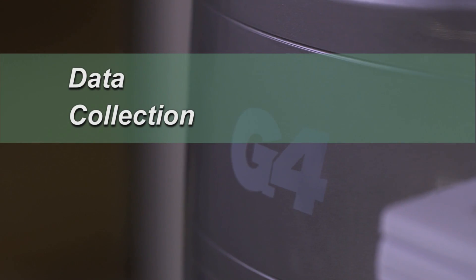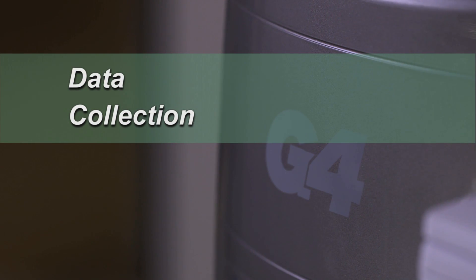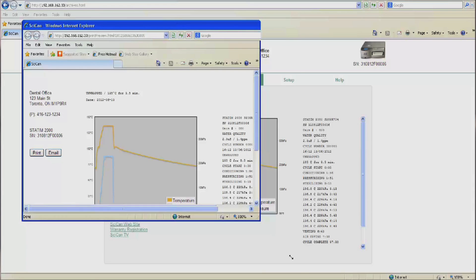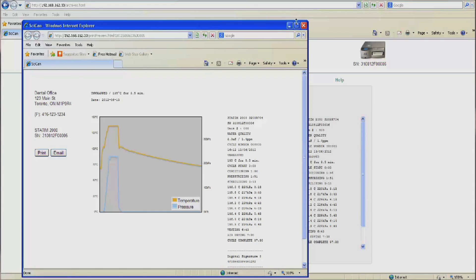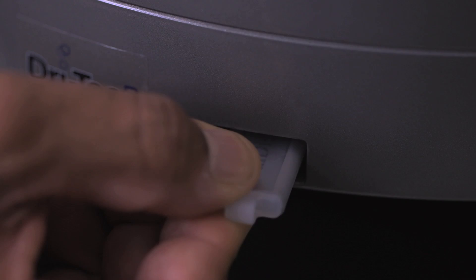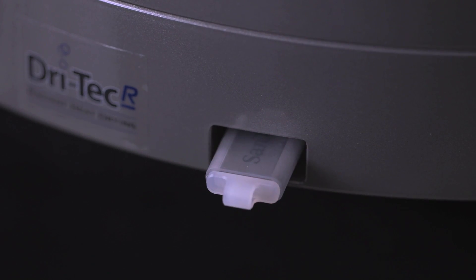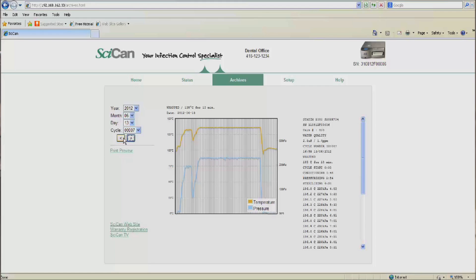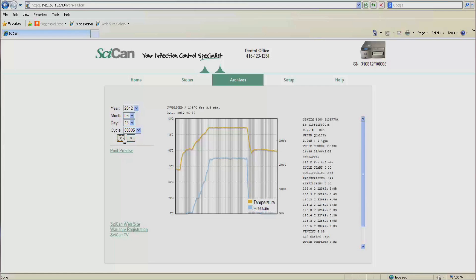Features like advanced data collection make managing information fast and efficient. Through the G4's networked portal, the Statim's current status can be viewed and all cycles and cycle graphs can be examined. Data logging is also automated. The USB flash drive engaged in the front of the unit will record all cycles and include the unit's serial number, date, cycle number, any error codes, and the confirmation of a completed cycle, including all times, temperatures, and pressure associated with the successful cycle.